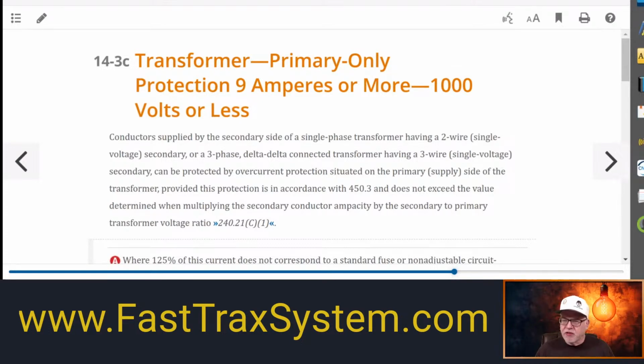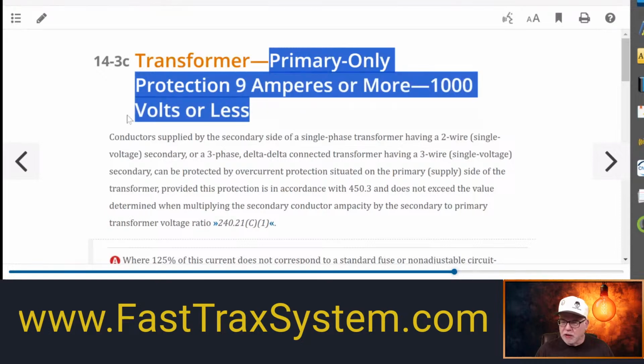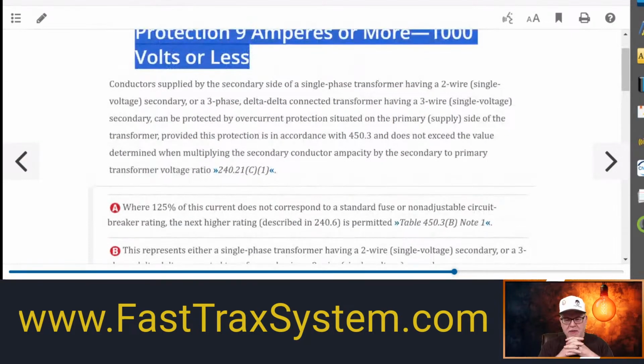So transformer protection. If we had primary only protection, and again, we're looking at the application, using table 450.3(B), and we're doing only primary protection. In that table, and I'll show you the table, we have the options for primary only protection, which means we would have no secondary protection. Under that, you have to meet very specific rules, right? And then, of course, you have primary and secondary protection. That's typically what we would run into. In that scenario, the primary protection could go up to 250%, and then your secondary protection would be up to 125%.